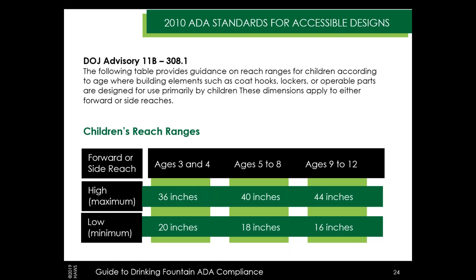Children's reach ranges are based on age ranges — remember children are defined as ages 12 and under in the ADA. Ages 3 to 4 have a high-low reach range of 36 to 20 inches; ages 5 to 8 have 40 to 18 inches; and ages 9 to 12 have 44 to 16 inches. Ages over 12 are expected to utilize adult height drinking fountains. You'll typically find children's fountains in school systems and daycare facilities. In public, the expectation is that an adult is present to assist the child.